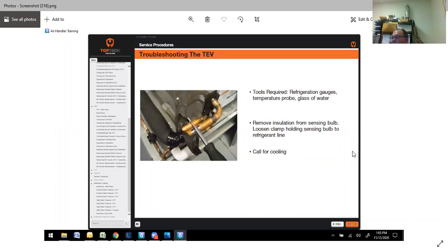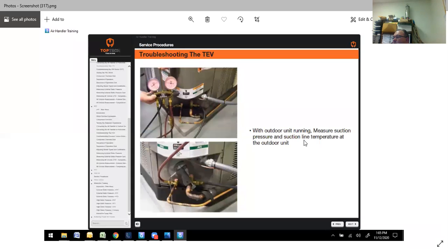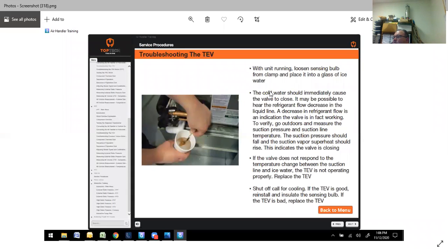But there's a couple ways to check this. Number one, obviously, you can tell by running the system, but there's another further way you can do it. What you're going to need is refrigeration gauges, temperature probe, and a glass of ice water. Remove the bulb from the suction line. Call for cooling. With the outdoor unit running, measure suction pressure and suction line temp at the outdoor unit. With the unit running, so you have an idea what it's doing, loosen the sensing bulb from the clamp and place it in a glass of ice water. The water should immediately cause that valve to close. It may be possible to hear the refrigerant flow decrease because it should be so dramatic. Decrease in refrigerant flow is an indication that the valve is in fact working.